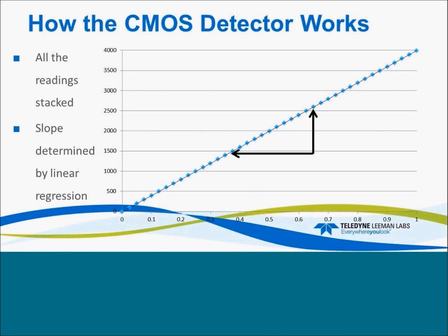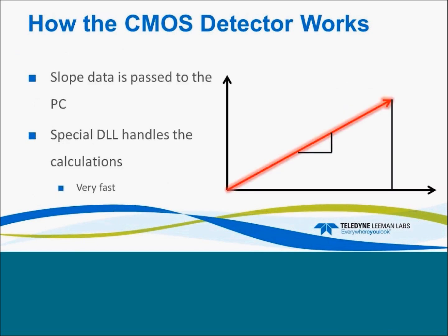And that gives us a much more accurate way of determining what the intensity is. On a perfect device, mathematically, we could go ahead and just measure intensities, but in a real device like this, we get better precision if we use a linear function or linear regression to determine what the intensity is. So basically, we have all these calibration curves, and we determine what the intensity is.